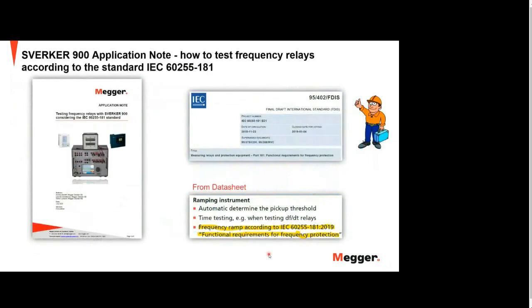So we have made an application note, which you can find on the Megger webpage, for example, about how to test frequency relays according to the standard IEC 60255-181. So you can read everything about this, how to test frequency protection with the Sverker 900.